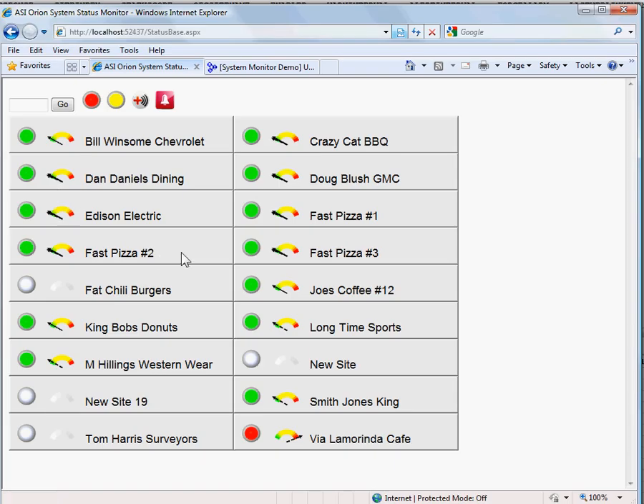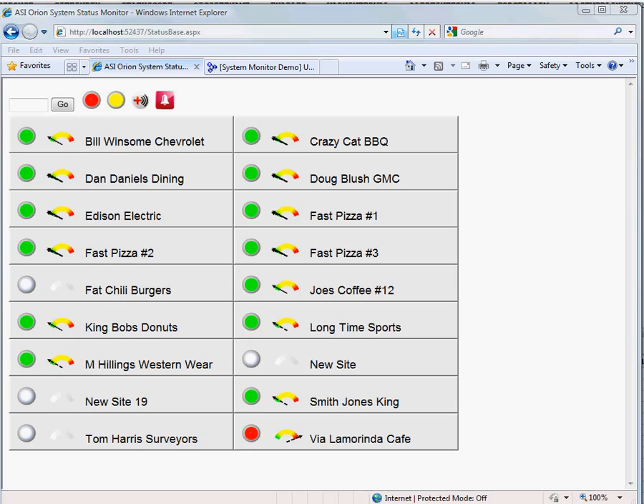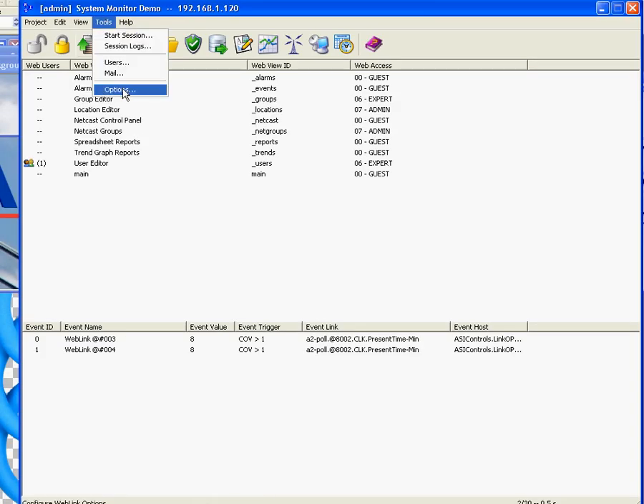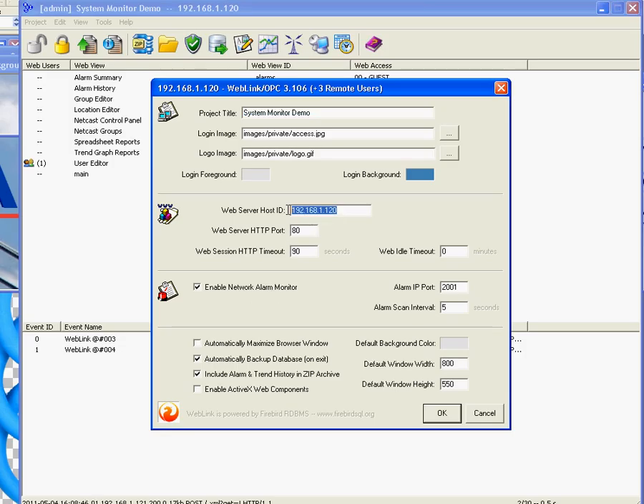We are going to look now at the setup, starting with ASI WebLink. Very fundamental stuff. You have to make sure you've got Enable Network Alarm Monitor on. We're going to note our IP address for the site is 1.120.